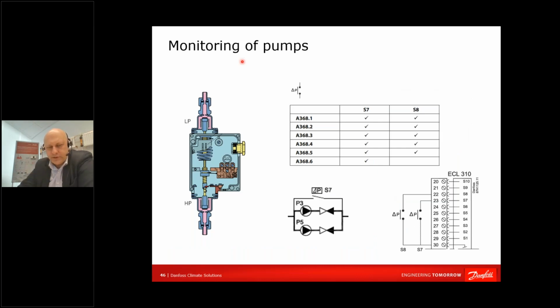A pressure switch to monitor whether the pump is running or not. You're just connecting the pressure switch to the ECL. As you can see, high-low pressure, where it is connected, and how does it work? For example, something had happened with a running pump. The pressure switch discovered that differential pressure is small. Then we have an alarm, and the ECL is switching on another pump, and you have to fix your pump which had been doing something wrong.